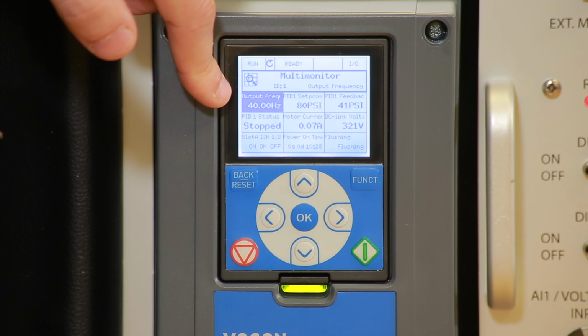Next thing is the power factor, and then the drive states. This is how the drive makes things simple for us. The drive says the next questions are for setting motor min and max frequencies and acceleration and deceleration ramp times. So if we have a submersible pump or some kind of application where we need dual ramp times and dual ramp speeds, we can also program this. So right now we want minimum frequency reference. This could be 0, could be 30, could be whatever you want it to be, 40 hertz. So we'll leave it at 0, but you can adjust it as you see fit.